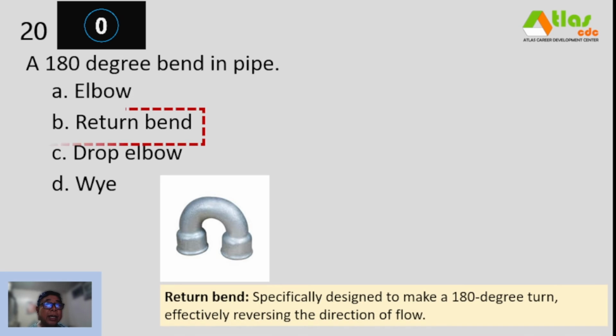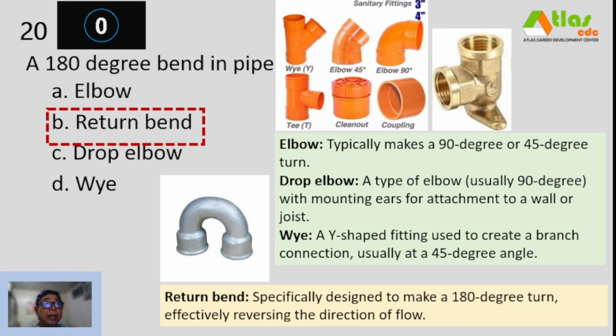And our correct answer is B, return bend. So specifically designed to make a 180-degree turn, effectively reversing the direction of flow. An elbow, this one, typically makes a 90-degree or 45-degree turn. So 90 or 45 degree. A drop elbow, this one is a type of elbow, usually 90-degree with mounting ears, for attachment to a wall or joist. And wye is a Y-shaped fitting used to create a branch connection, usually at a 45-degree angle.